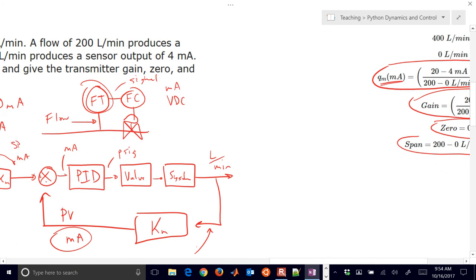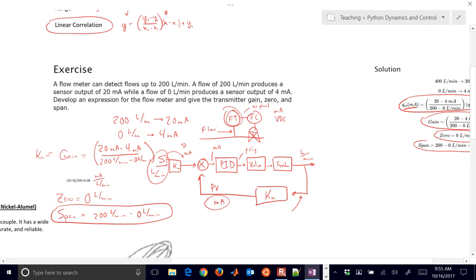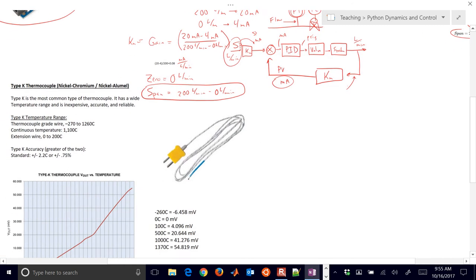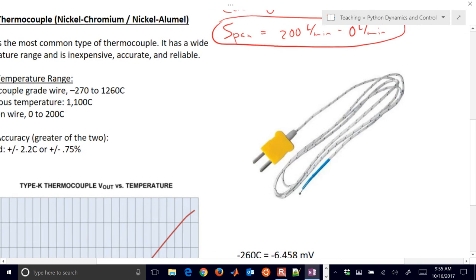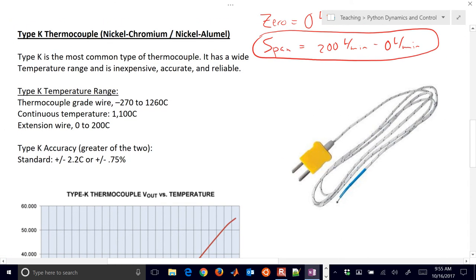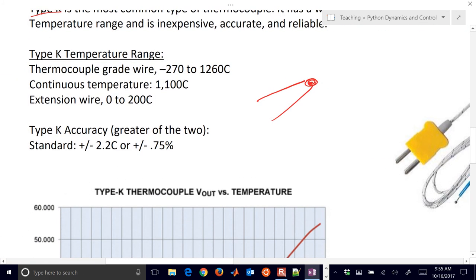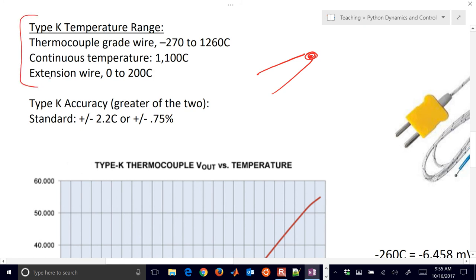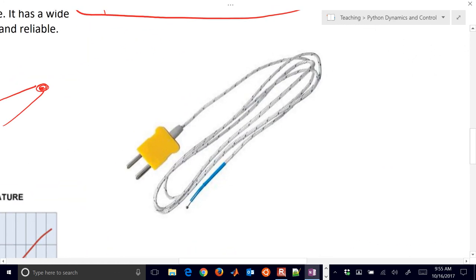So let's go on to, I want to talk just a little bit about a very common type of sensor that's used in a lot of processes. And this is the type K thermocouple. So this is a joining of two dissimilar metals. Two dissimilar metals with this bead. And on one side, you're going to have a nickel chromium and the other a nickel alumel. And the type K is probably the most common type of thermocouple. It has this wide temperature range and is inexpensive, accurate, and reliable. Just a little bit of information about a type K thermocouple. And you can see a picture of it right here.